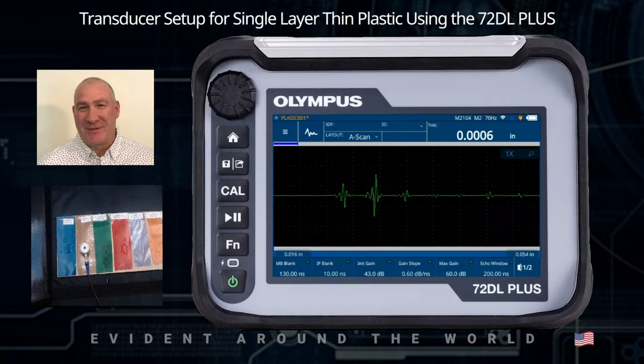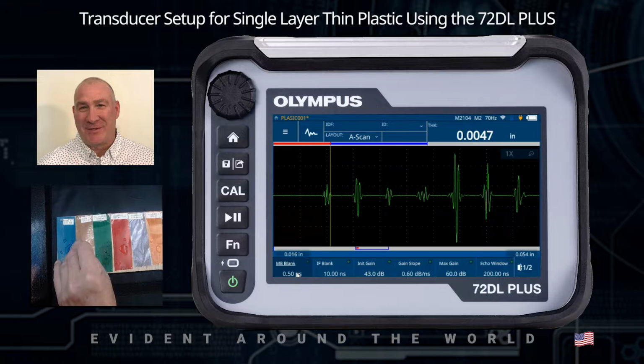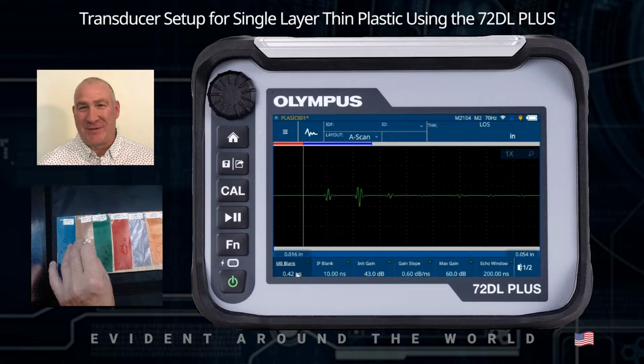So if I touch on main bang blank, I can then use the adjustment knob in the top left-hand corner, and I can start to increase this. And as you can see, I'll slowly start to see that move out. If I want to make quicker adjustments or coarse adjustments, I can click it again, and you'll see that it'll start to move a lot faster. So single click is for fine adjustment, a double click underlines it, and it's for coarse adjustment. Now, that's a little too far out, so I'm going to just turn the knob back a little bit, and there we go. Okay, so we're already starting to make detection of echoes.